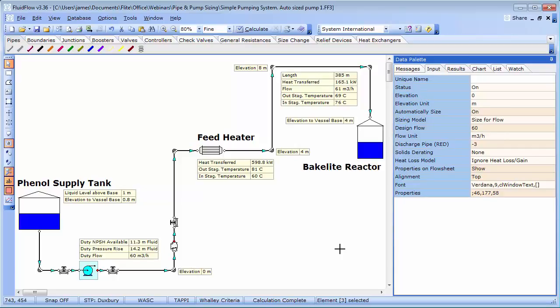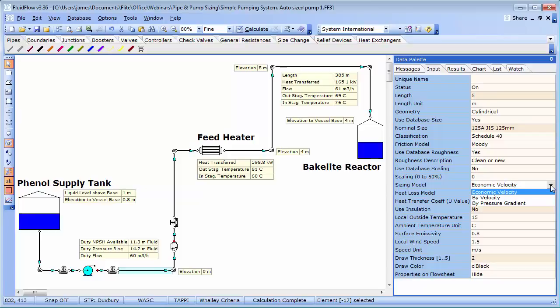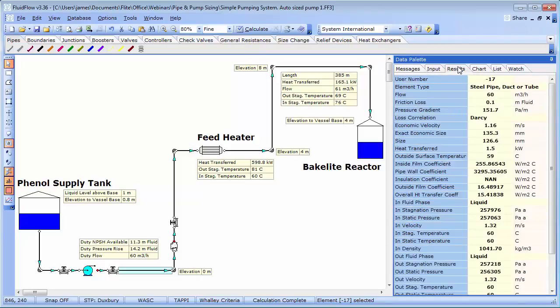We have a number of options to choose from to automatically size our pipework. This includes economic velocity, a design velocity or design pressure gradient. We are going to choose economic velocity as we wish to develop an economic system design. By calculating the model, the software has determined an economic velocity of 1.16 metres per second.